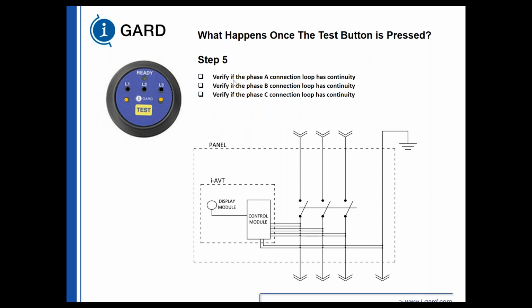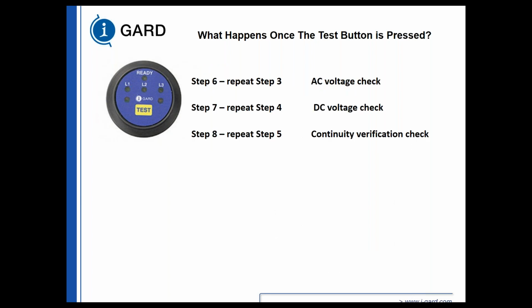Step 5, verify that A phase, B phase, and C phase are still connected the way they should be. Step 6, repeat the AC test. Phase to phase, phase to ground. Step 7, repeat the DC check. Step 8, repeat the continuity check. So we've checked the voltage phase to phase and phase to ground twice. We've checked the continuity of the circuit twice.